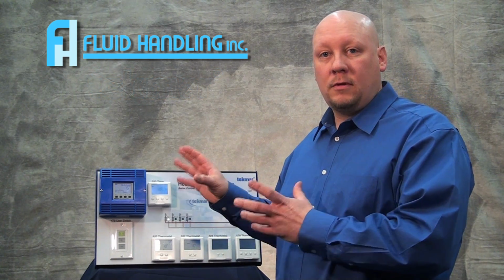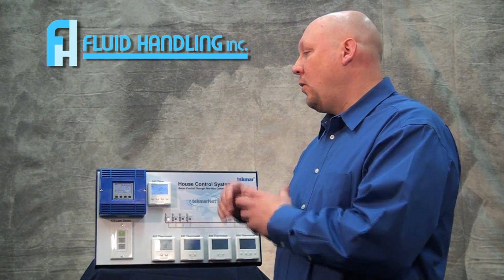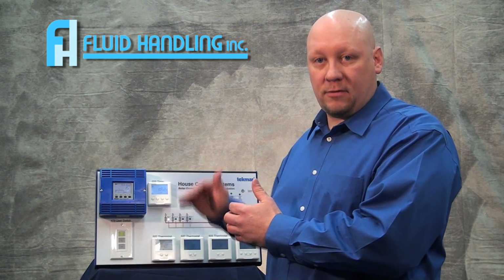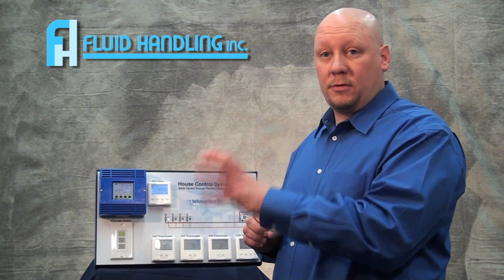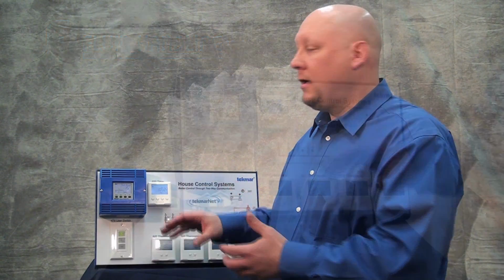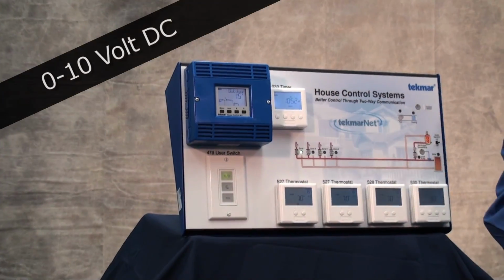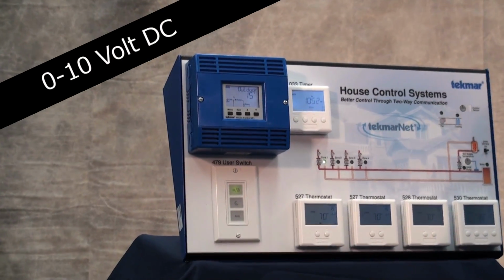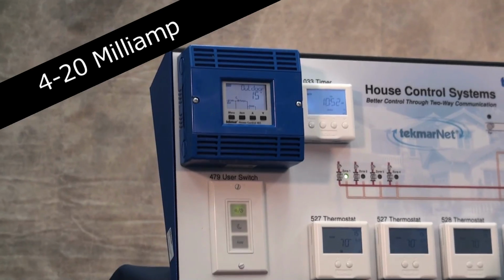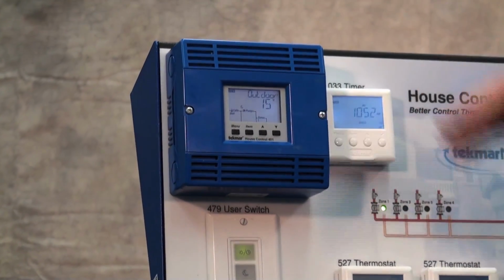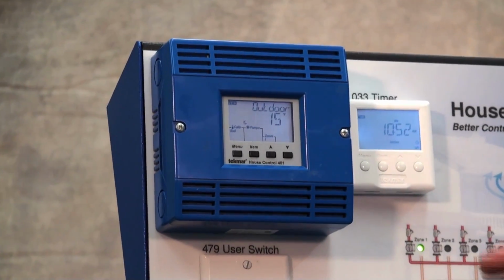With the 400 House Control series, what we're doing is, with a ModCon boiler, Tekmar will take over the modulation of the boiler. So you will need to go into your boiler control, tell it to accept an external signal. The Tekmar 400 House Control works with either a 0 to 10 volt DC signal or a 4 to 20 milliamp signal. We can tell it in here which one you have.